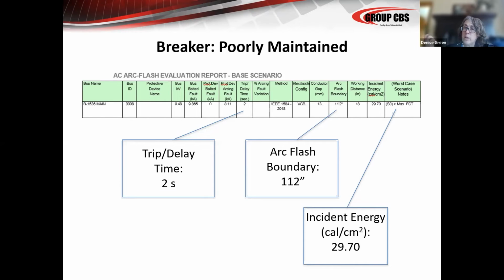The incident energy available is ramping up exponentially during a fault. It's not linear, and you've crossed into a very dangerous situation in a very short amount of time. So I wanted to give you the view of the exact same breaker with just a change in trip delay time. And then you can imagine, if the breaker partially opened and you had a situation going on, that incident energy would end up even higher.